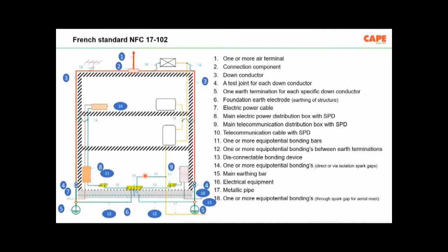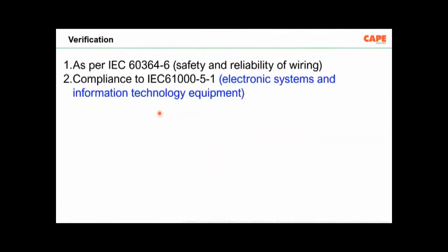The standard recommends a proper equipotential bonding system. The French code explains a proper equipotential bonding system. Whereas in a lot of places, what happens is the rod is there, one down conductor, one earthing. Item numbers 2 to 18 are missing. Only one rod, and most of the time with long wires. So you forget it, it won't work.